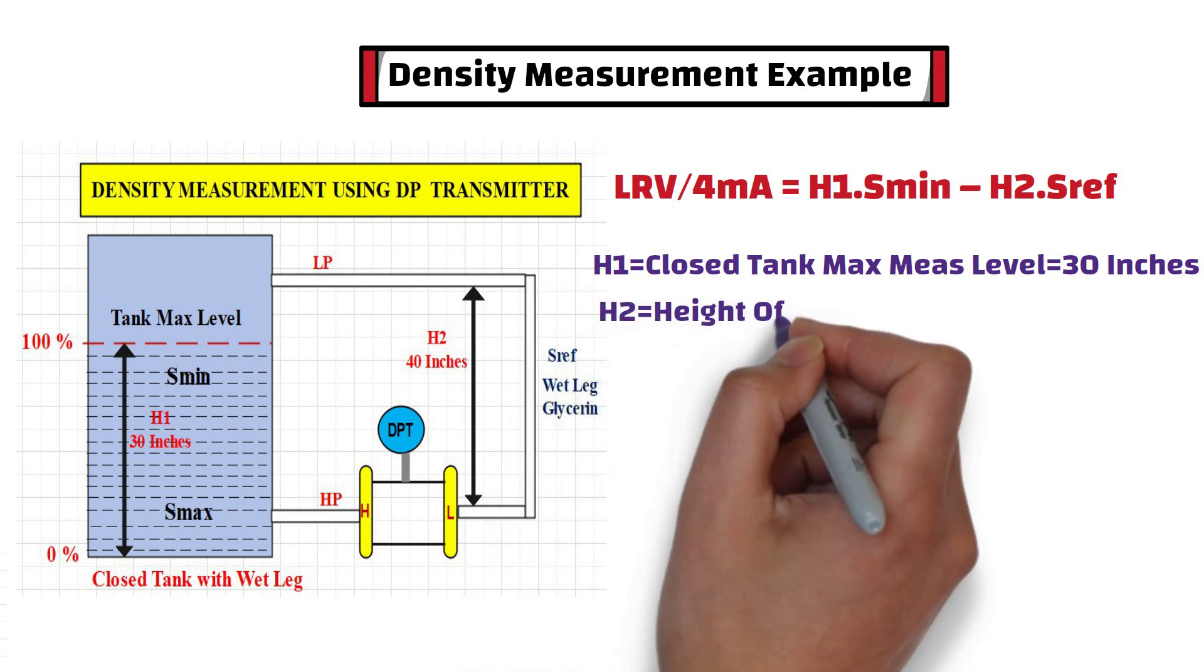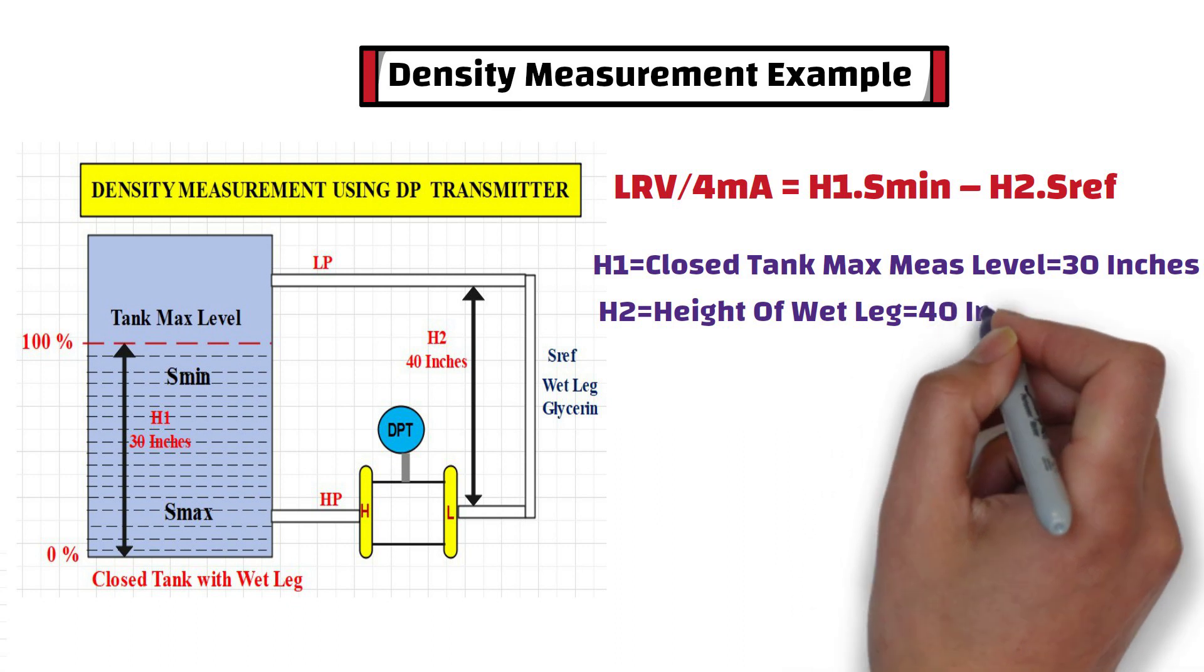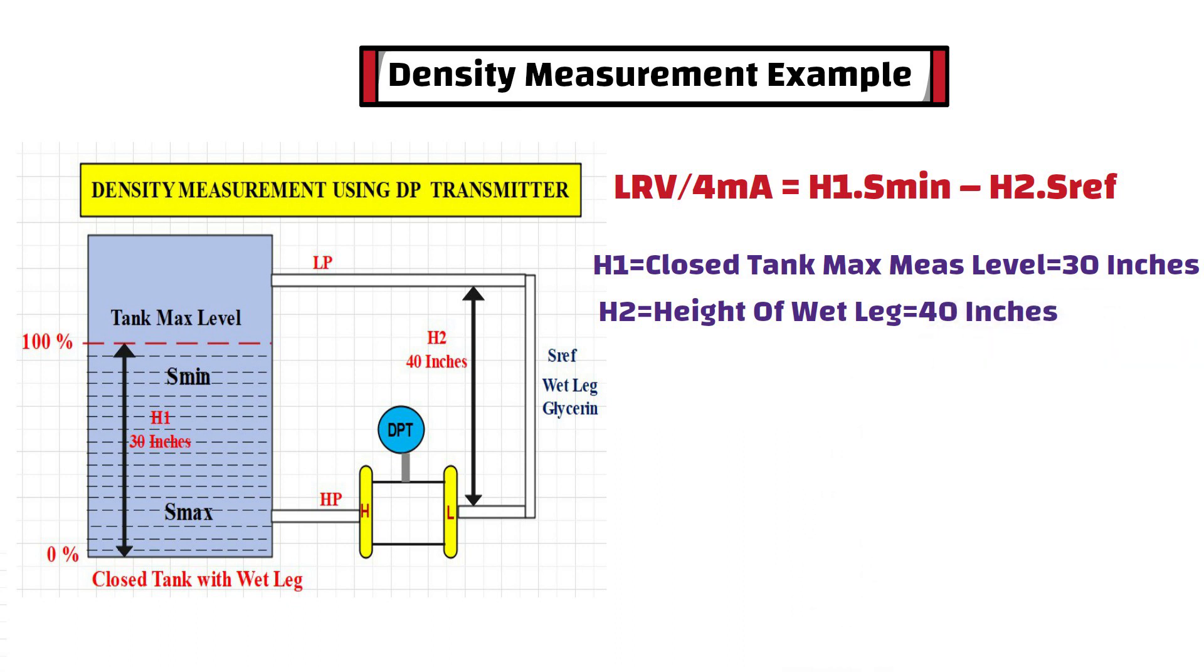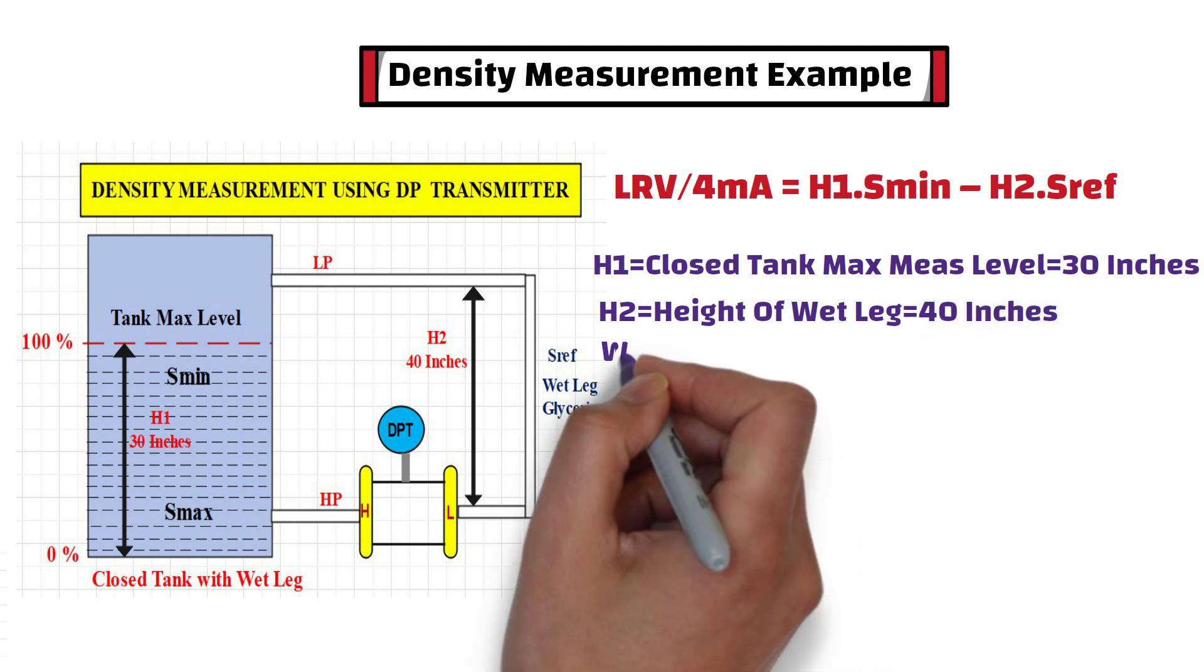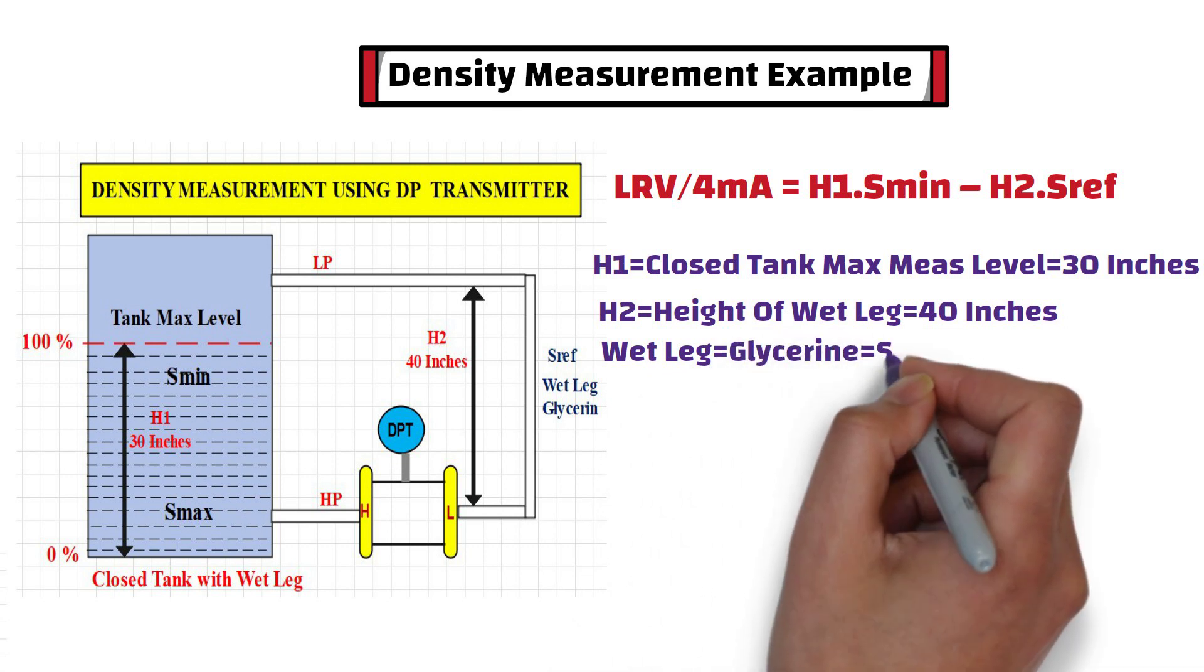H2 is the height of wet leg. In this example, wet leg's height is 40 inches. The wet leg is filled with glycerin, and its specific gravity is 1.263.